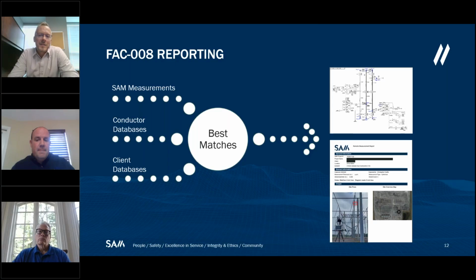Each page of the FAC-008 report identifies one single element inside the substation. Typically, we'll work in bays, like a 230 kV substation, where equipment needs to be identified in 4 or 5 of the bays. So we'll try to use nomenclature that's easy for the engineer we work with to tie this report back to specific equipment inside the substation.